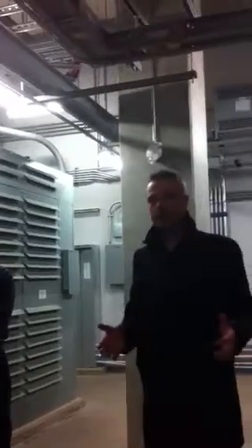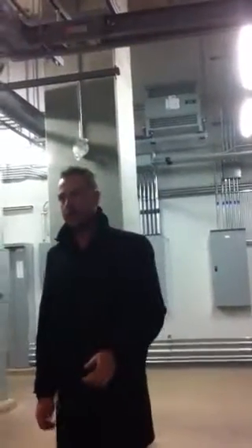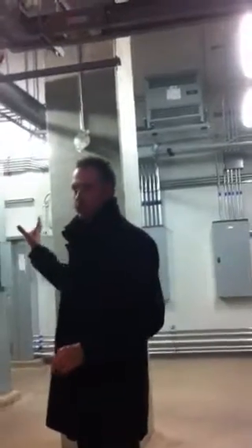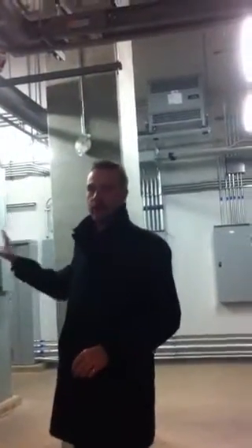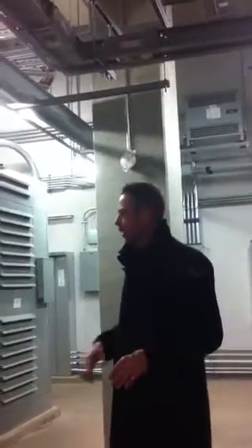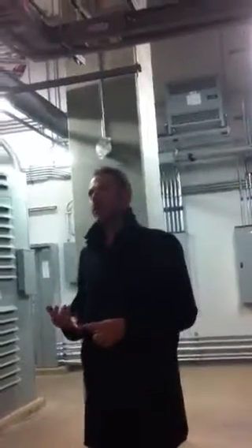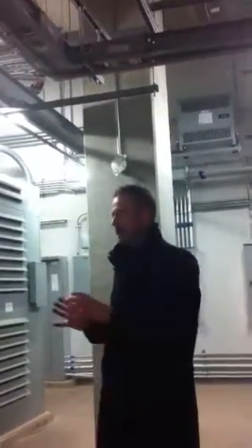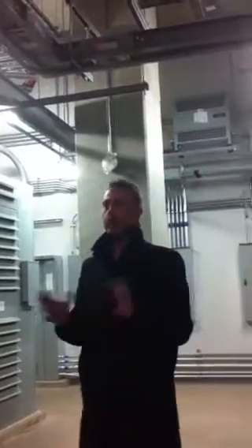The room with the transformers and the primary gear has a lift-out well roof, come with a crane, and it's a big concrete block. You pull the concrete block off with a crane, and you can crane the equipment down into the room. Again, even though the Schulich expansion is still, the loading dock is there, and they're just starting on the main slab of the infill, all of the electrical gear for that building, and subsequently all of the electrical gear going into that building, sized large enough in order to feed the entire engineering complex, is already in place. It's not hooked up physically, wired into the ring main yet, but all of the equipment is in there, and they are building the building essentially around the electrical equipment on the lower floors.